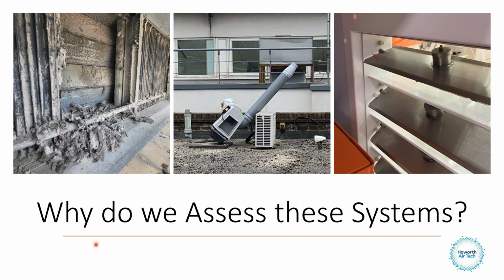You can see the AHU intake on this air handling unit here is disgusting. It's obviously full of lint or some sort of, I don't even know what it is. It's obviously not up to scratch for a critical ventilation system. The middle picture there, even if it was stood up, wouldn't be compliant because this discharge stack is blowing straight into your face - that's probably attached to a fume cupboard. It's exposed to the elements, and it's also fallen over and it's sat on this DX unit over here.